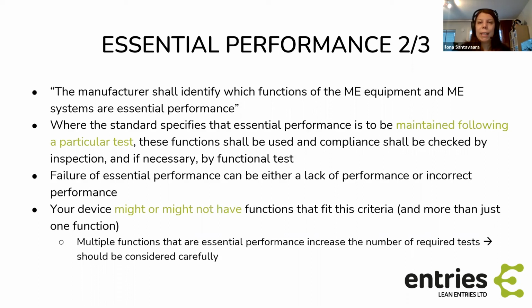And then there are places in the standard where it says that essential performance is to be maintained following a particular test. So, yeah, failure of essential performance can be either lack of performance or incorrect performance. And it's good to note that your device might or might not have functions that fit this criteria. So not all electrical medical devices have this kind of essential performance. But on the other hand, if you do have essential performance in your device, you might have multiple functions.